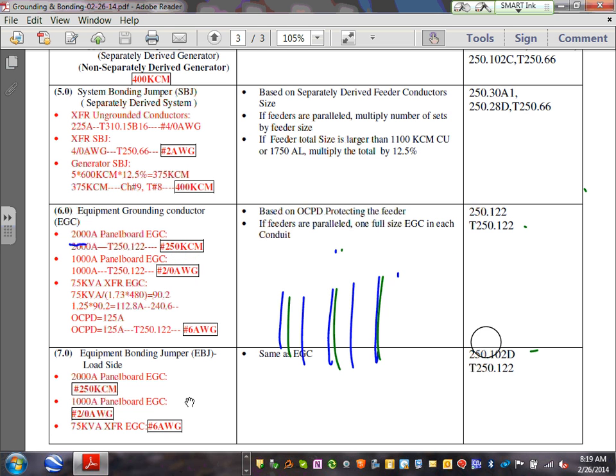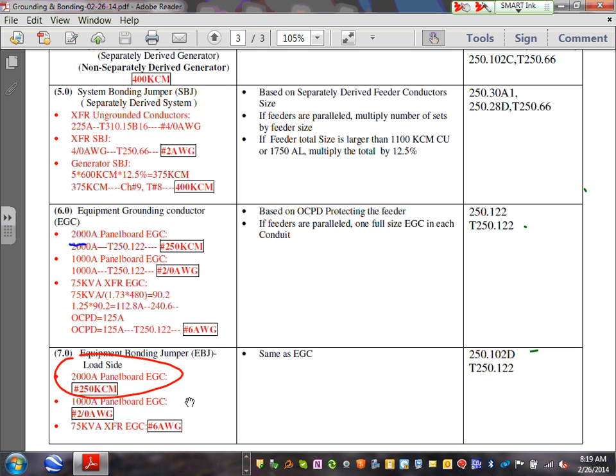That's kind of a weird term. This is when they bond the conduit to the switchgear. It could be the same cable. Number 7 is the same size. Can you guys see it's the same as an equipment grounding conductor? Everybody can see that? So I made it easier for you. When you have an equipment bonding jumper, it's the same as an equipment grounding conductor.